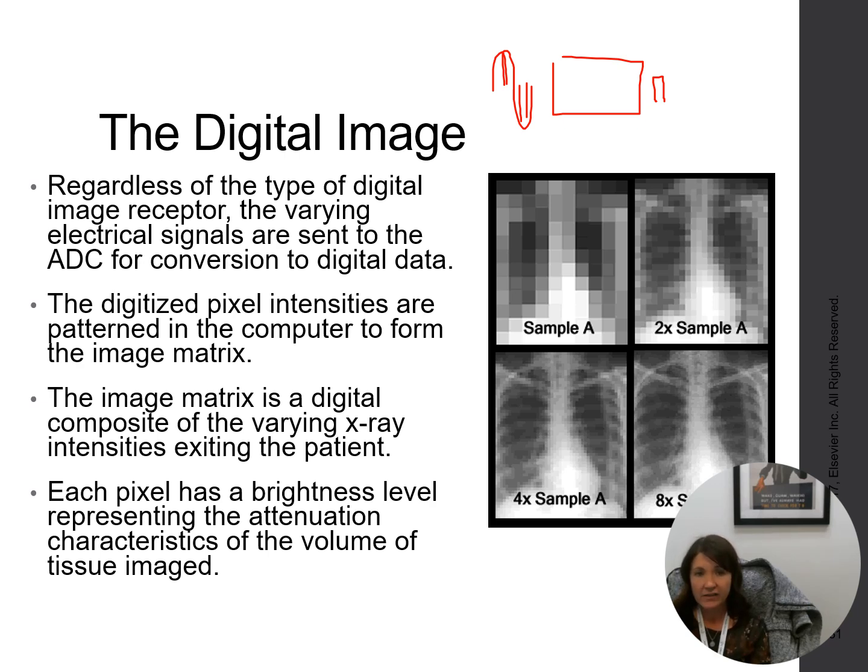And that digital value signal is then going to be counted up and plotted on a histogram. But it's also going to be maintained in order. So if it occurred in the upper right lung, we don't want that signal to appear on our image in the lower left lung. So it is going to have to follow its spatial domain, stay organized, get plotted on this histogram, and yet still end up with that gray signal in the appropriate digital placement on the display.